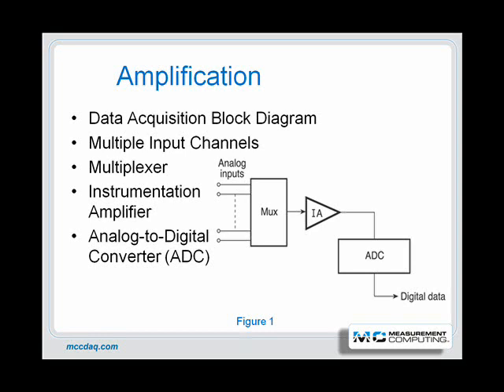ADCs selected for data acquisition systems typically run from 20 kHz to 1 MHz and have a resolution of 16 to 24 bits. They also have either unipolar or bipolar inputs. The unipolar type typically ranges from 0 volts to a positive or negative voltage, such as 5 volts. The bipolar type typically ranges from a negative voltage to a positive voltage of about 5 volts as well. Many data acquisition systems can read bipolar or unipolar voltages to the full resolution of the ADC, but they need a level-shifting stage to let bipolar signals use unipolar ADC inputs and vice versa.